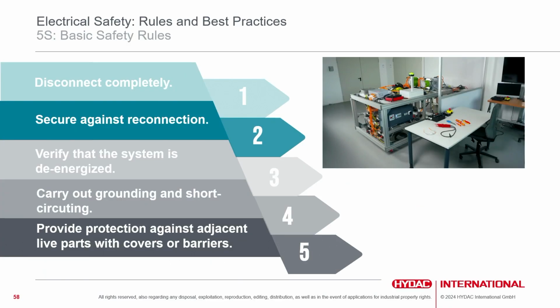Okay, two comments about points 4 and 5. Especially with mobile systems, you have to really make up your mind whether it makes sense to follow rules 4 and 5. For example, grounding and short circuiting doesn't make sense when talking about a battery system - you clearly should not short circuit a battery system just to make sure the rest of your system is not energized anymore.